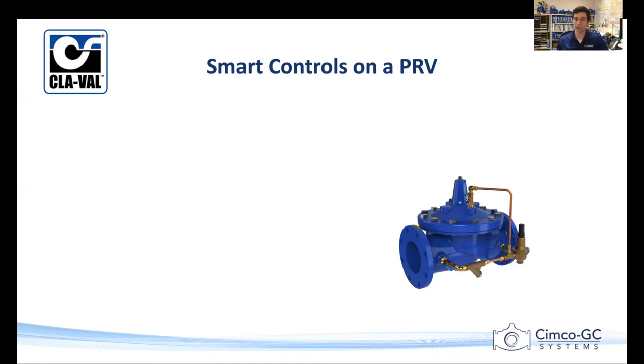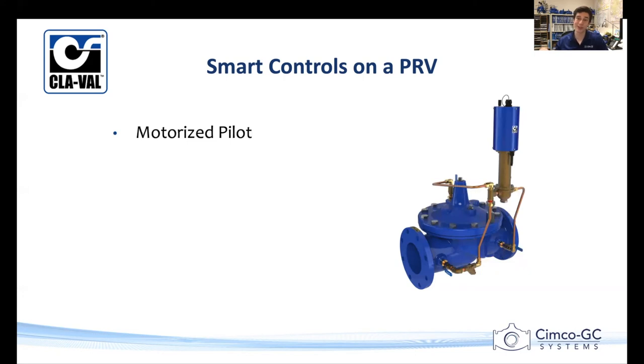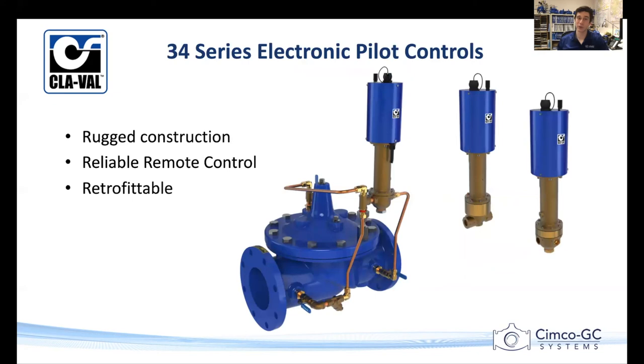A way to make this valve a little bit smarter would be to add a motorized pilot. So we're going to take our same pilot, but put a motor on it so that we can change that set point on the spring. This is our 34 series of electronic pilot controls, where it's taking the same body, but adding a motor on top of it. These are really useful because it's the same proven technology. If you lose power, it just operates in its last position as its normal pilot, but you can also remotely change it. So if you want to change your set point for night and day, you can do it with one of these pilots. If you want to change your set points based on the season, no need to go to the vault, just change it electronically and it'll adjust the tension on the spring.